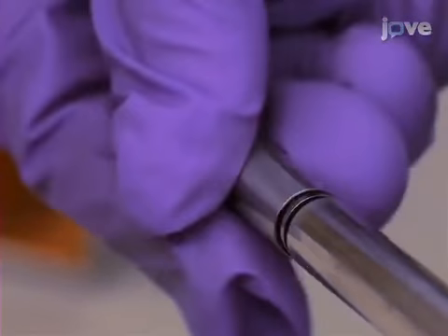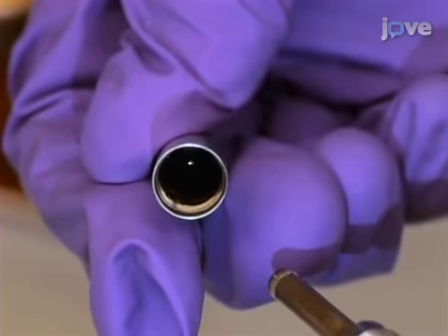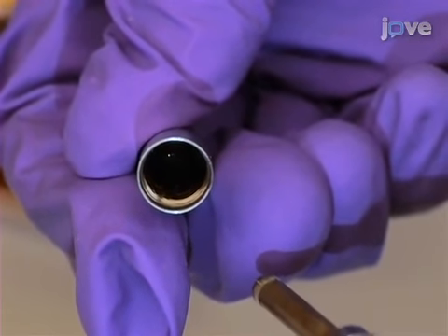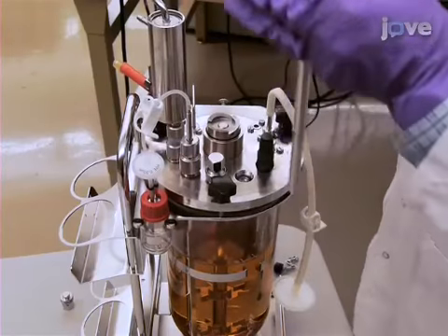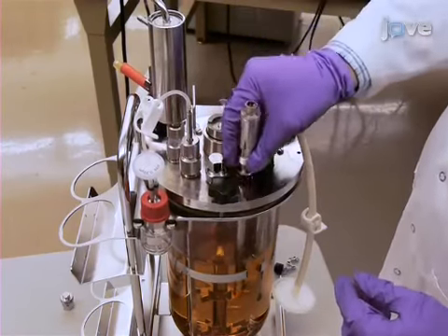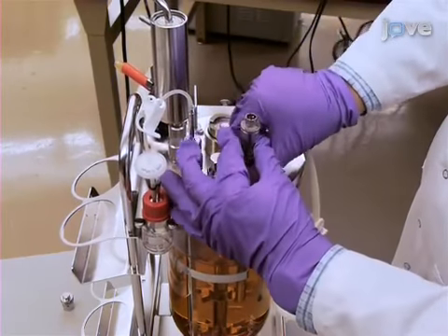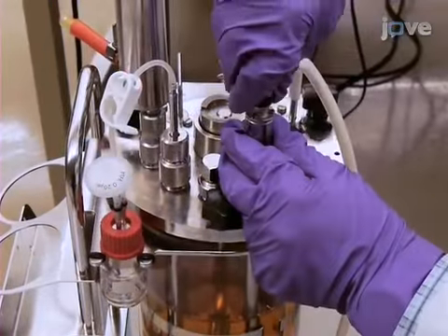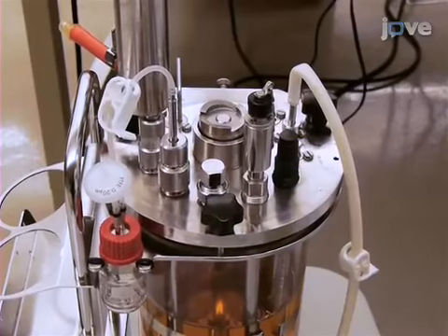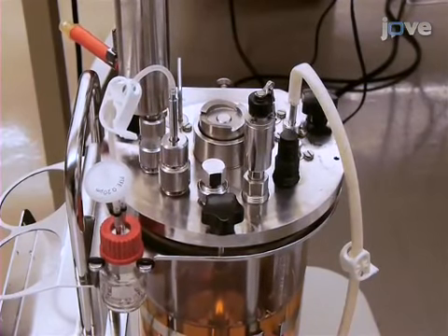Open the oxygen probe tip and check to ensure that there is enough electrolyte to cover the tip. Install the oxygen probe in the head plate. Make sure the autoclave cap is put on to protect its electrical connections, as it will be sterilized prior to calibration.